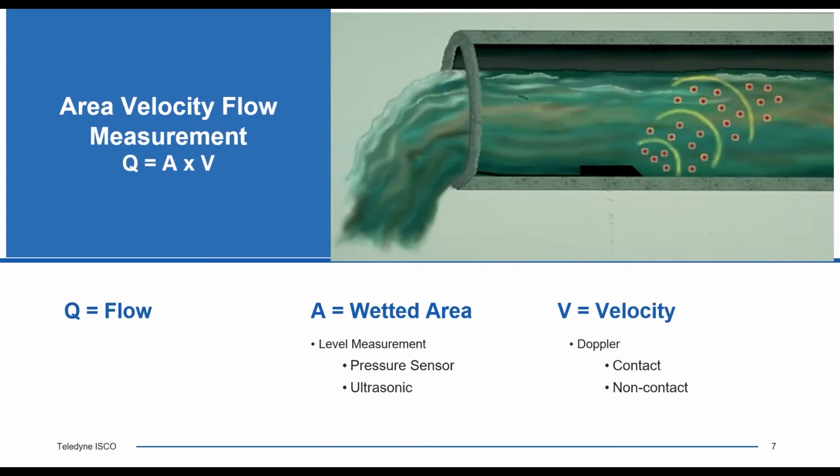There are a couple types we're going to talk about, but one in this case is the contact type. When I refer to contact, I'm referring to a sensor on a ring that's in a pipe. These are the most common ones that you would see out there, and they have been around for many, many years. This picture gives you a good example of what this thing actually does. You'll notice the level measurement is that blue line. It's sensing the pressure over that sensor, and it transmits a frequency out the nose. Everybody has a slightly different frequency, but that's what it's doing: transmitting, getting a return signal back, and averaging what comes back from that measurement.